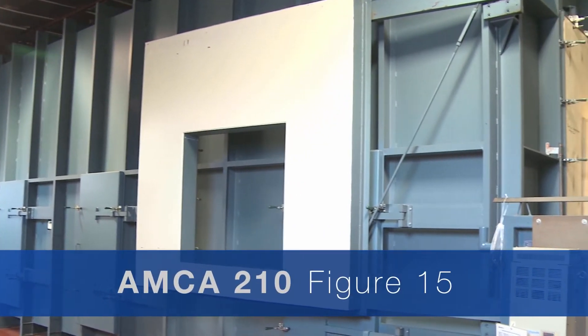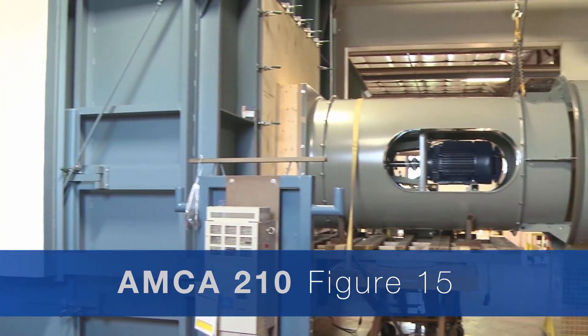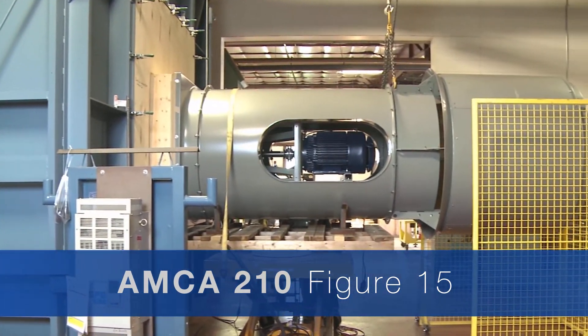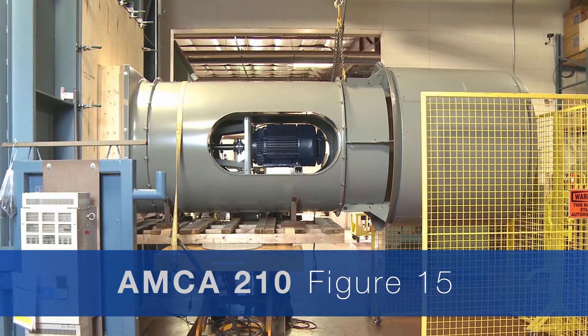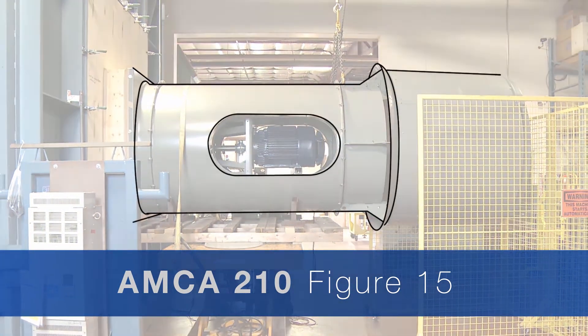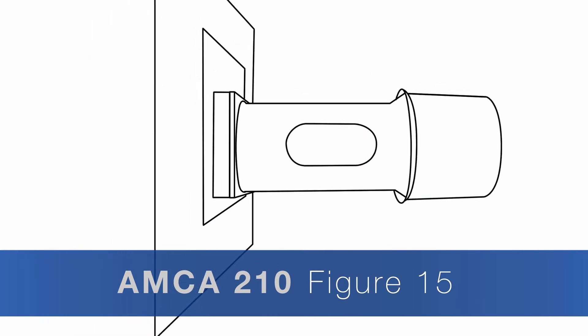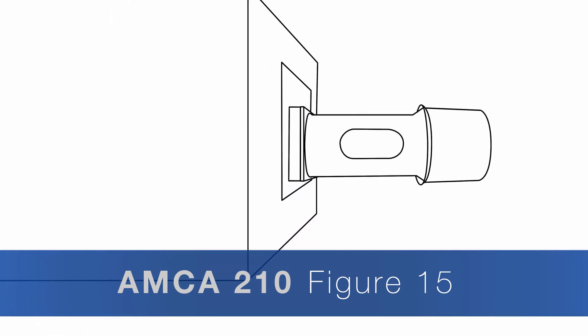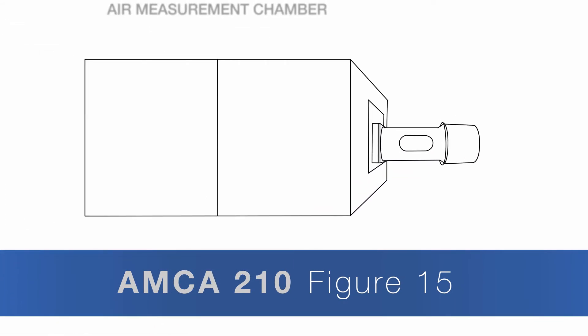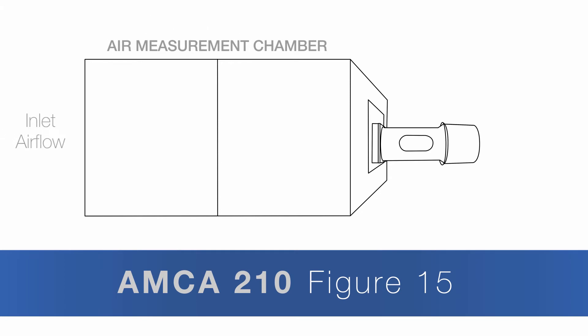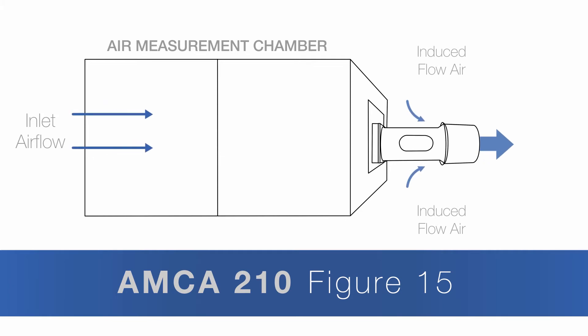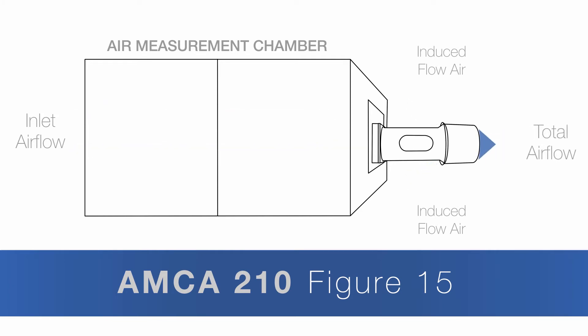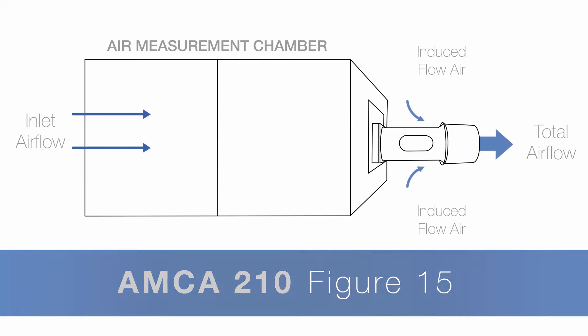Initially, the induced air fan is installed in an AMCA 210 Figure 15 configuration. In this configuration, the fan's inlet air performance is measured at different static pressures utilizing an air measurement chamber. This provides information on what air volume is going through the fan's inlet. This is the first step of what is needed to determine performance for an induced air fan.